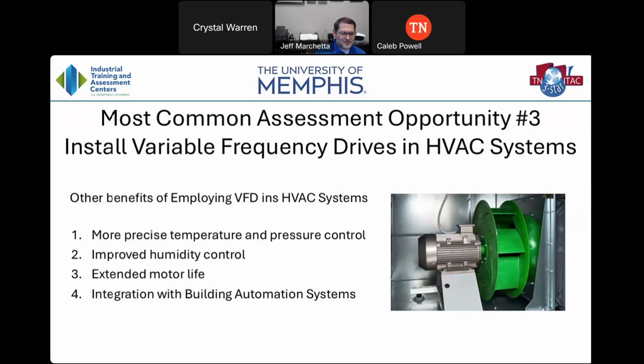So the benefits of the VFD - I kind of mentioned some of these. Very precise temperature and pressure controls, humidity control, because instead of starting and stopping your fans, you have a continuous airflow over your cooling coils, and much better control over your humidity in terms of the evaporation process and how much is going to be lost to condensation.